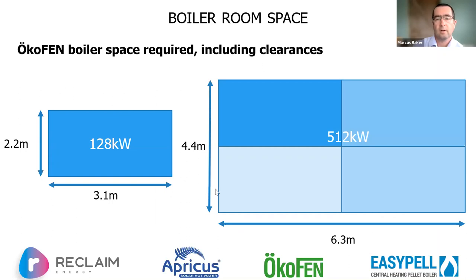So if we look at the space required, including clearances for 128 kilowatts, it's about 2.2 by 3.1. And so in theory, you can just push them as close together as possible, just having the minimum clearance around each one, and get half a meg for 4.4 by 6.3 meters, which is a bit more than 24, 25, 26 square meters. It's not a great deal of space, and you've got a half a megawatt of output. That doesn't include the pellet store.